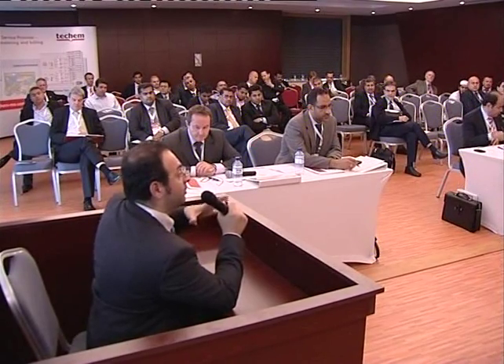Before we build any plant or community we need to deliver, we draw up a very reliable, strong assessment, mainly from the redundancy point of view, especially redundancy of chilled water. District cooling is much better than standalone systems, because there is momentum in the water — it already holds a certain amount of cooling. Exerting that through heat transfer, especially with underground pipes, takes time, and the time elapsed depends on the network size and dimension. The bigger the network, the greater the economy of scale, and the more you can deliver chilled water even with a shut down plant, compared to a smaller network.